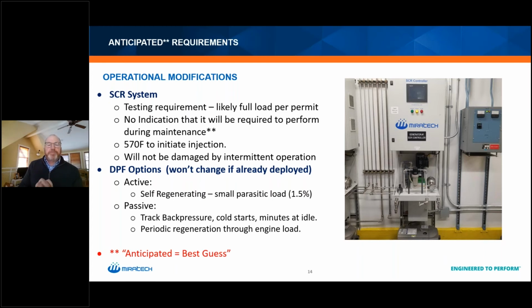What we think is going to happen is, if your data center operator likes to exercise their engines at no load for half an hour every two weeks, we don't believe this rule is going to make you change that necessarily. Why that's important is any SCR system needs about 570 degrees Fahrenheit - it's a catalytic converter, and the chemistry only works with heat. It needs about 570 F to come on and do what it's supposed to be doing for NOx reduction. You're probably not going to hit that in your half hour at no load, so when you're exercising your engine, you likely won't get any NOx reduction.